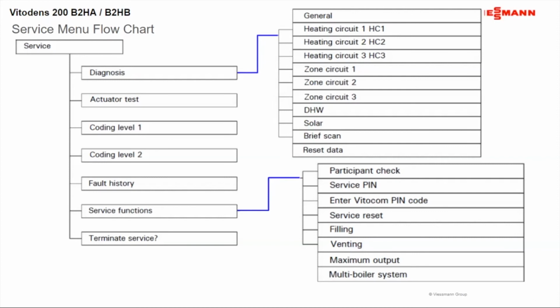Multiple boiler system, that's where you're going to go in there and click OK on that. That's if you're doing multiple boilers, because you can do up to 8 boilers on a cascade system with these 200s here. Cascade 8 and common vent 4, and use one cascade control to run all the boilers. It would reboot and go into a multi-boiler setup on the screen. That's a different class.